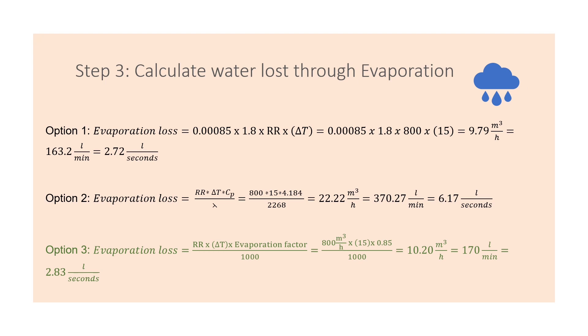And lastly there's the third option to get evaporation loss whereby it just looks at the evaporation factor, the circulation rate, and the change in temperature divided by a thousand. If you punch everything to calculator you should get the water loss through evaporation in the form of meter cubed per hour. Assume that the third equation is more accurate and efficient. Let's work with it moving forward.